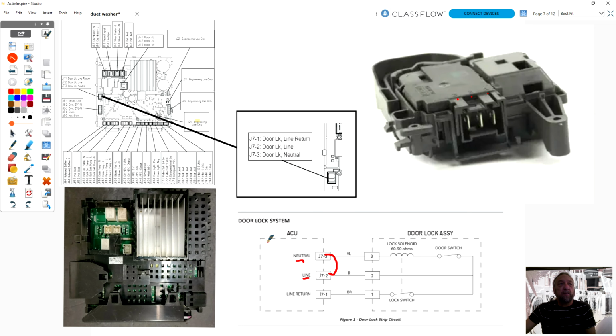But if we look at this, let's just say I checked red to yellow and I opened and closed my door. I closed the door, I got 90 ohms. That means what? The lock solenoid is activated. Not that the lock solenoid is activated, but the door switch is closed. We are measuring ohms through the lock solenoid, and we have resistance based on the schematic. We don't know if the solenoid's working, but electrically it ohmed out.